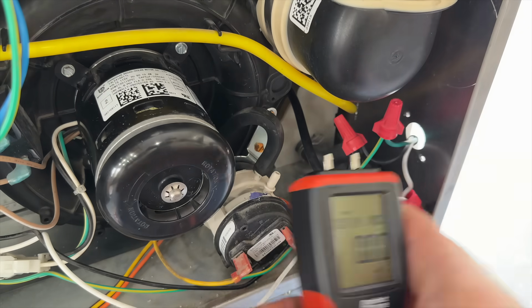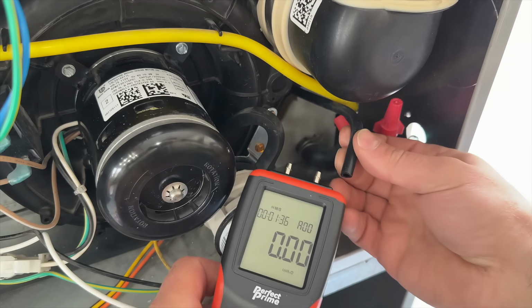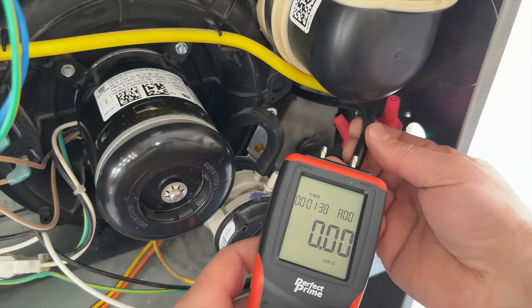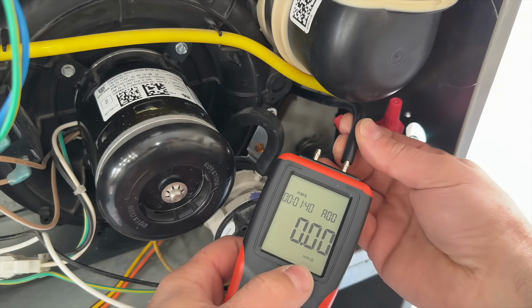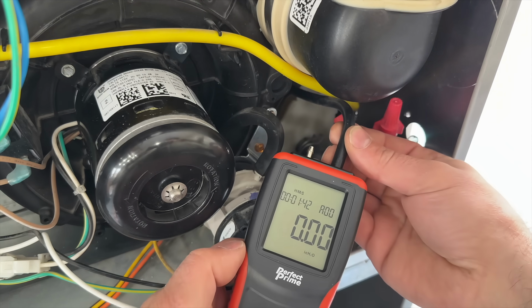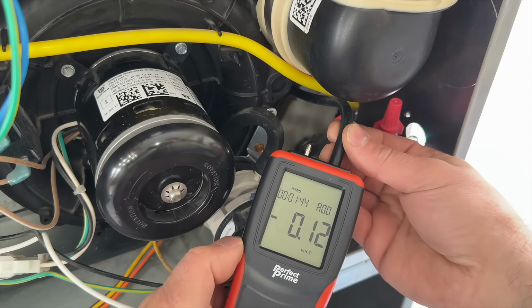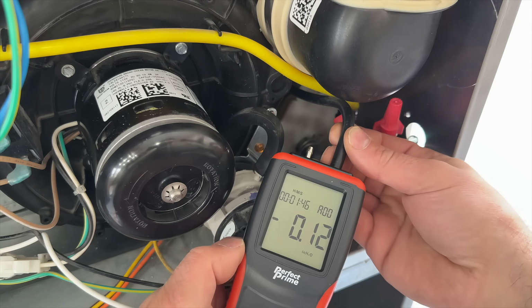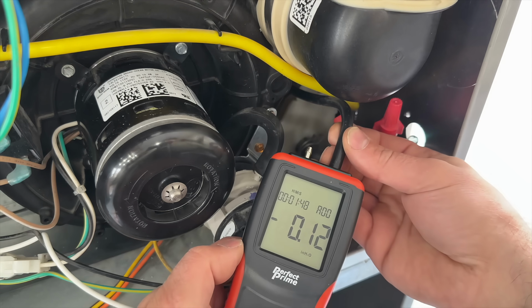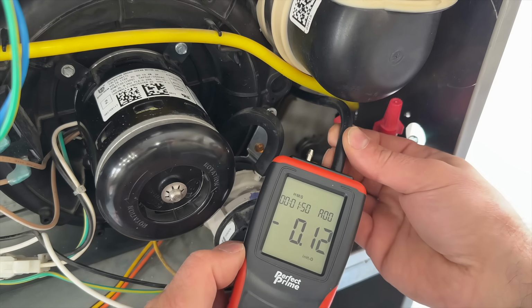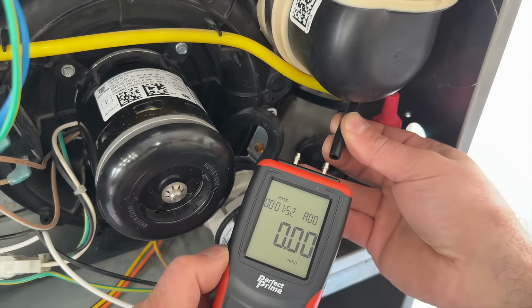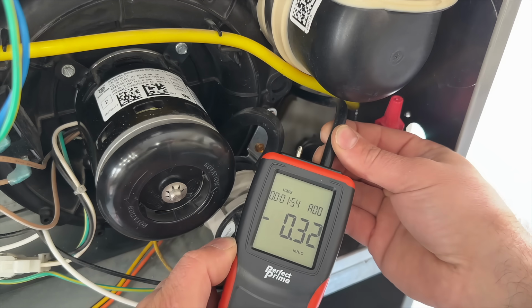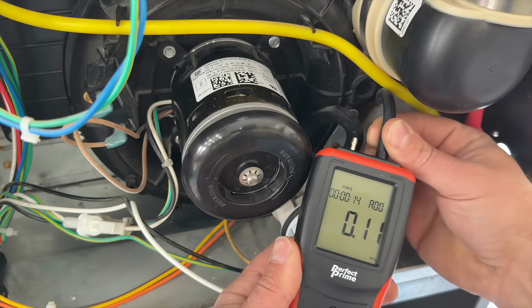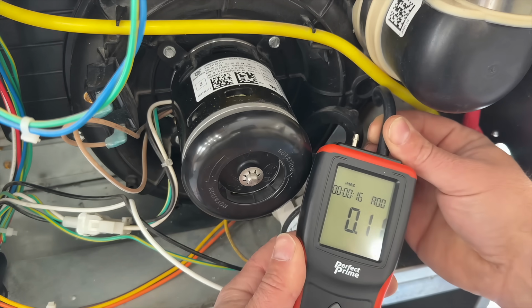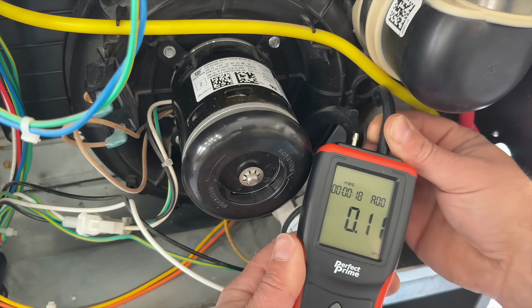Okay, so test number two, now that we have a crack in the heat exchanger, check this out. So we're reading 0 inches water column. As soon as we attach this, we have movement. It's very minimal, 0.12 inches of water column, but we do have movement when we connect this when we shouldn't. Before, we were reading zero. So again, this proves conclusively that we do have a crack in the heat exchanger with this method.